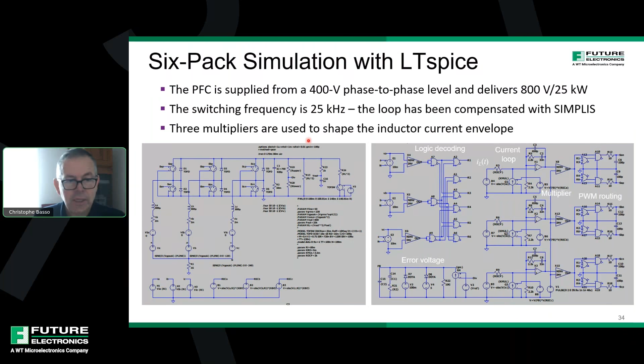In this example, the power is first set to 12.5 kilowatts and suddenly increased to 25 kilowatts. The nominal deviation is only 12 volts, which corresponds to roughly 1.5% of the nominal output voltage. The crossover is set to 100 Hertz, and this value is made possible in the absence of, of course, low frequency ripple as in single-phase PFC.